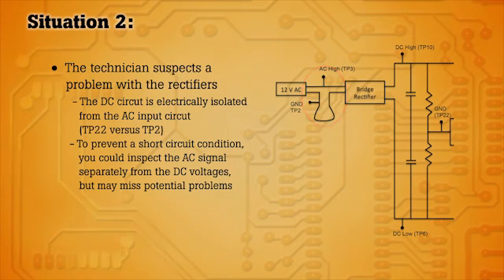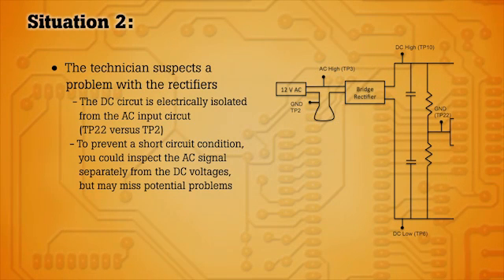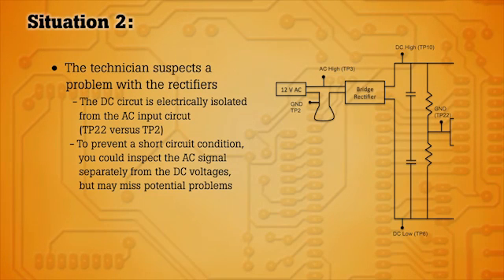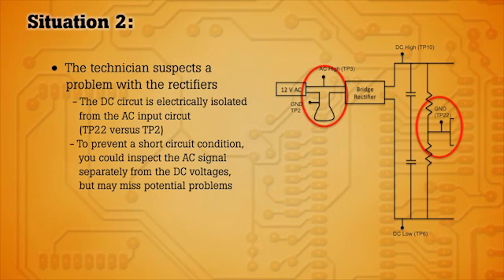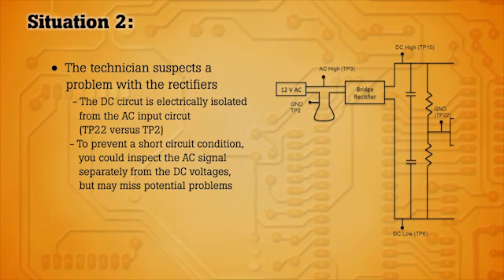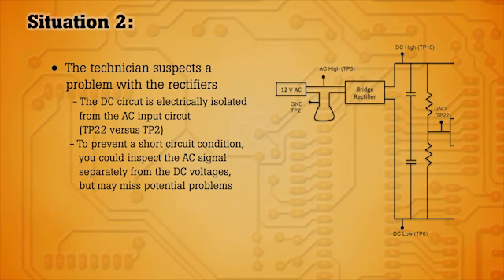To troubleshoot that circuit correctly, it's best to use an isolated input oscilloscope like the Scope Meter 190 series. This will allow you to look at both circuits simultaneously without causing a short circuit and damaging the rectifier or yourself.